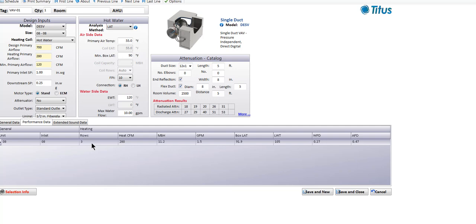As long as we're talking about coil rows: in terminal units, our one- and two-row coils are cross-flow circuited, meaning there's no difference in performance with regard to direction of air flow. This allows these coils to be flipped over in the field to reverse the connection locations with no change in performance. Once you get into a three- or four-row coil, it makes sense to take advantage of the added depth, and these coils are counter-flow circuited — we bring the water in at the leaving air side so the warmest water contacts the warmest air for highest heating efficiency. But most engineers don't want three- or four-row coils due to the air pressure drop.